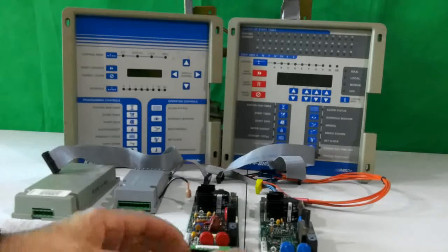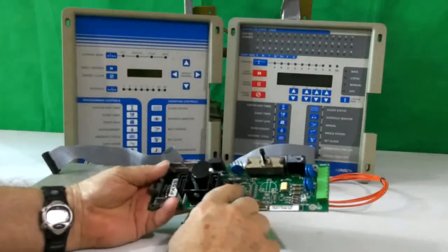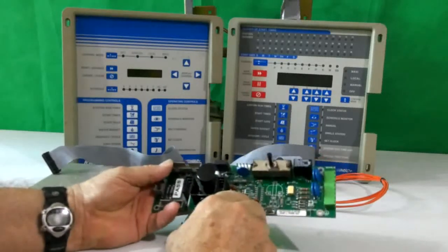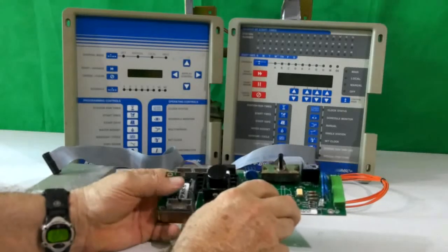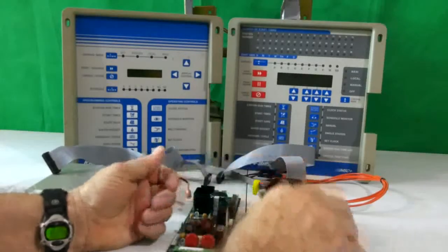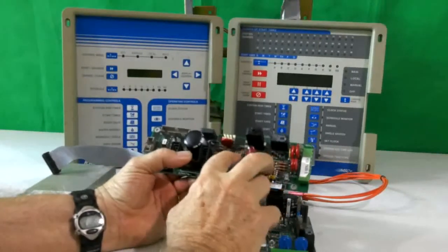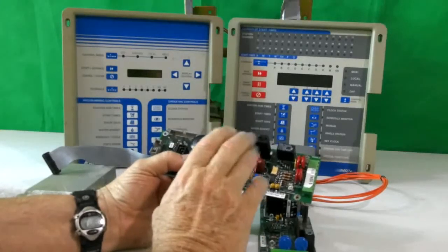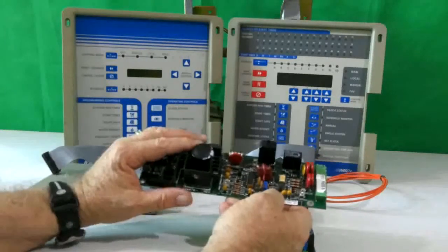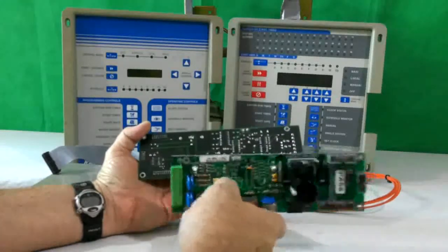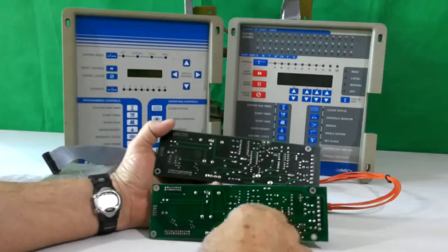What I have here are two different power interconnects. One is for the PAR Plus series. You'll notice that it's fairly simple, fairly light on electronic components. It works extremely well on the PAR Plus series, but it lacks the support componentry to get into the diagnostics of the MSC unit. The MSC power interconnect, as you will notice, has many more components in it, different chips for different sensing functions, so that it can perform the diagnostics that the face panel is capable of doing. If you're looking at these units, they're normally uncovered in a case, so if you look at them from the bottom side, you'll notice that the MSC has many more components soldered through the board than you will see on the PAR Plus.